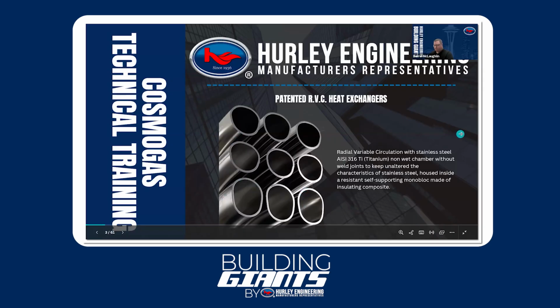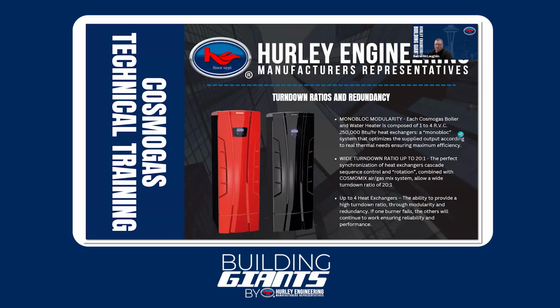You can see here the two main products: the boiler in the black and the water heater in the red. Primarily, this is a modular design. What that means is they offer a heat exchanger in each one, but we can stack up to 4 heat exchangers. If we started at a 250,000 BTU boiler, that would be a single heat exchanger. We can go up to 4 heat exchangers, and now we have a 1,000,000 BTU boiler.